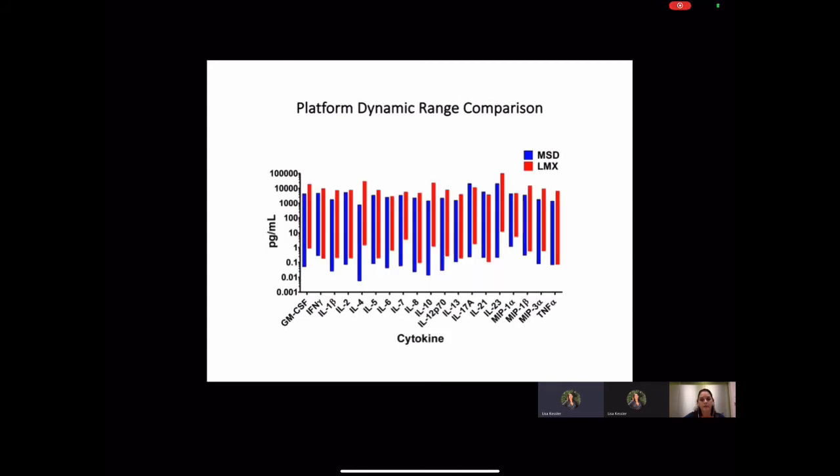We also compared the dynamic ranges for the 19 shared analytes in order to assess the sensitivity differences between the platforms. We extended the standard curves and added extra blanks to evaluate the limits of quantitation. We found the MSD platform, here shown in the blue bars, had a lower lower limit of quantitation for 17 of the 19 analytes, whereas the Luminex platform, shown in the red bars, had a higher upper limit of quantitation for 17 of the 19 analytes.